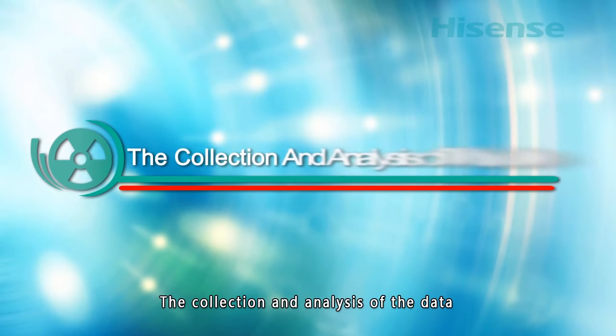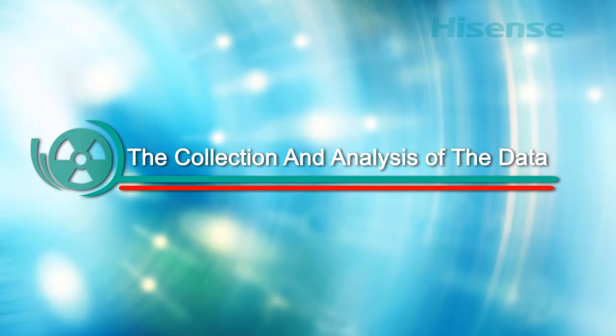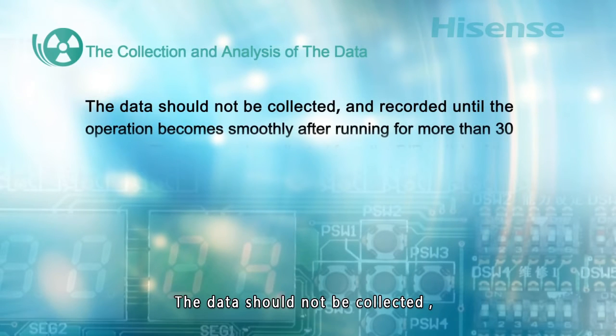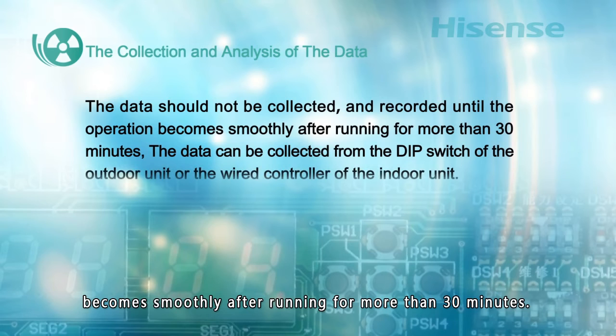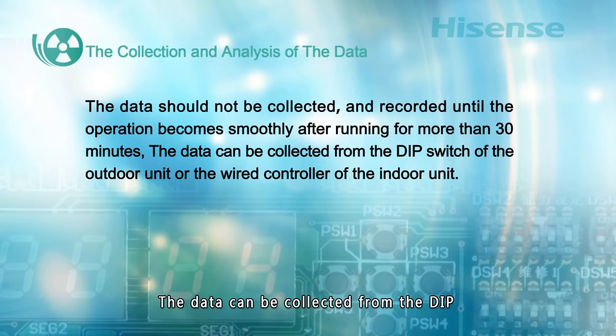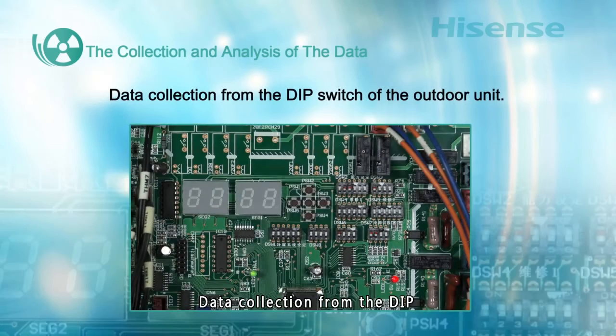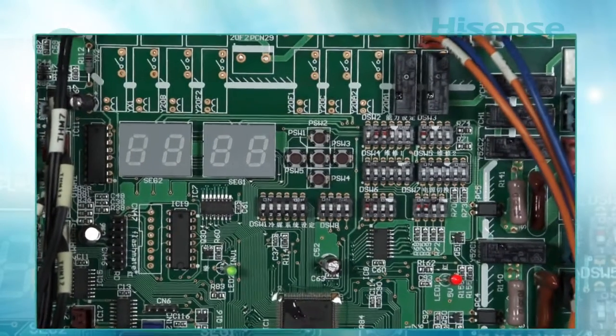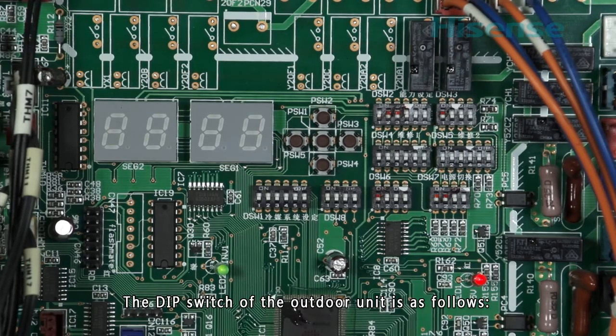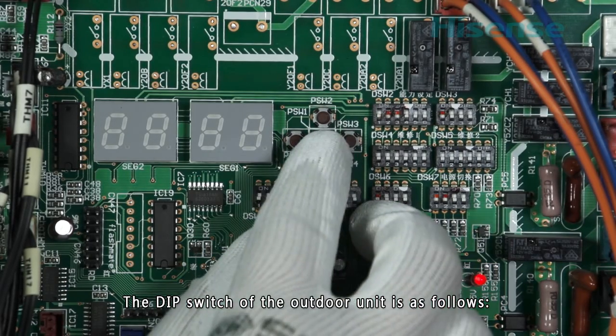The collection and analysis of the data. The data should not be collected until the operation becomes smooth, after running for more than 30 minutes. The data can be collected from the dip switch of the outdoor unit or the wired control of the indoor unit. Data collection from the dip switch of the outdoor unit: the dip switch of the outdoor unit is as follows.